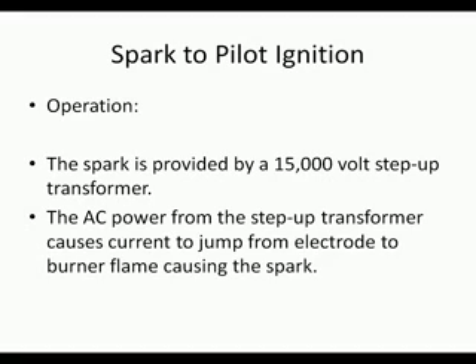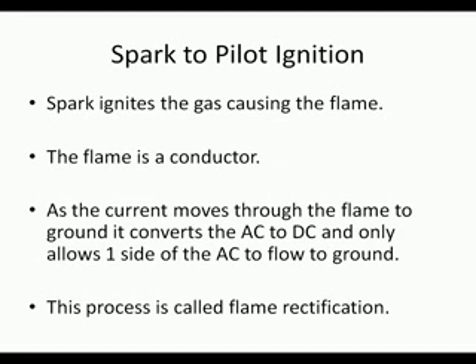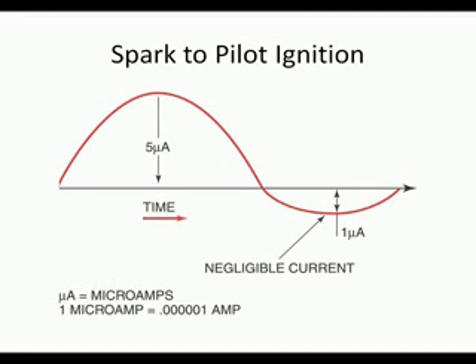When the pilot is lit, the flame is verified and the main burner is allowed to open. The spark provided is a 15,000 volt spark provided by the step-up transformer. The AC power from the step-up transformer causes current to jump from the electrode to the burner flame and causes the spark. The spark ignites the gas, causing the flame. The flame is a conductor. As the current moves through the flame to ground, it converts AC to DC and only allows one side of the AC current flow to ground. The process is called flame rectification.